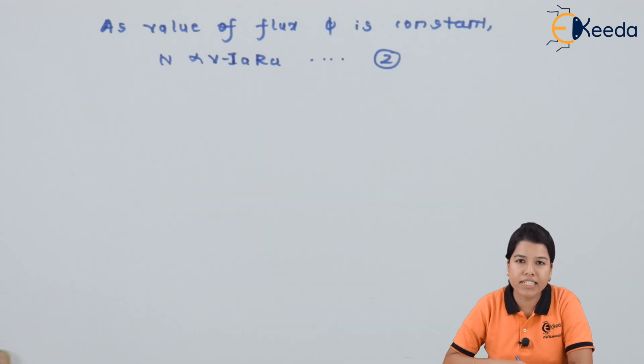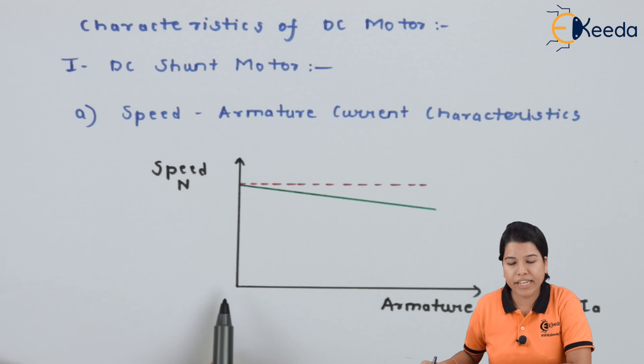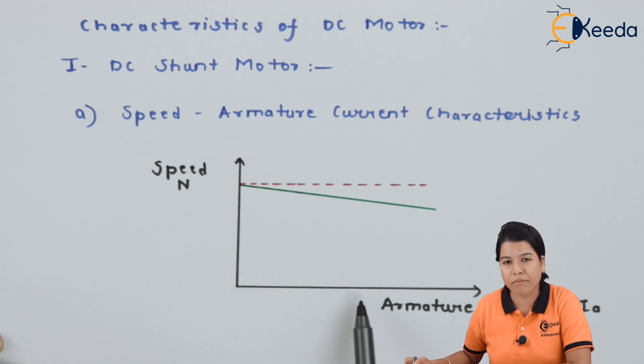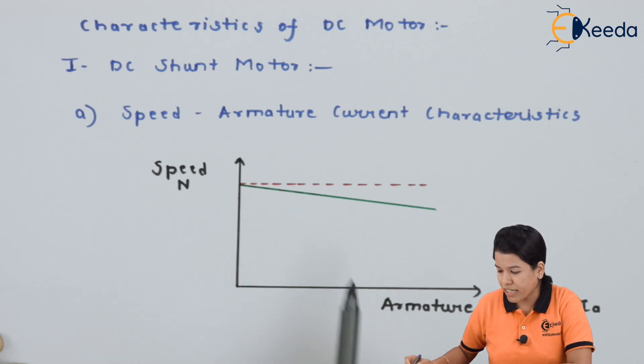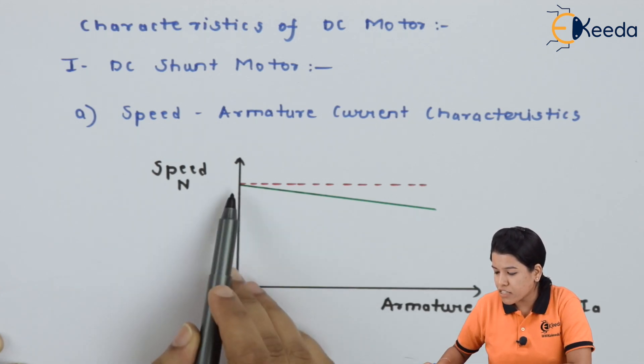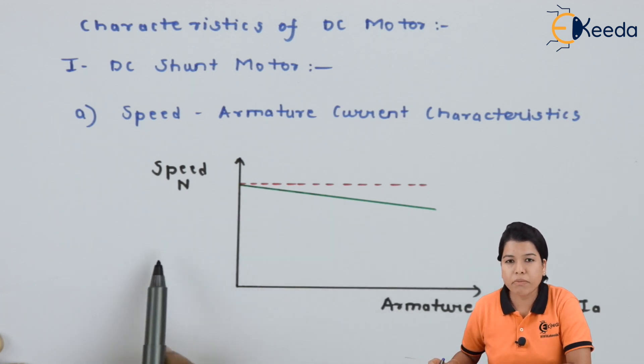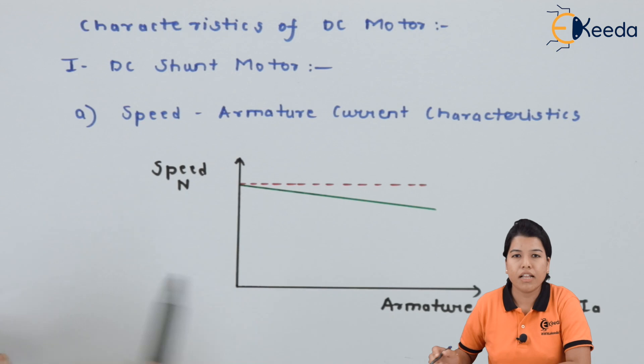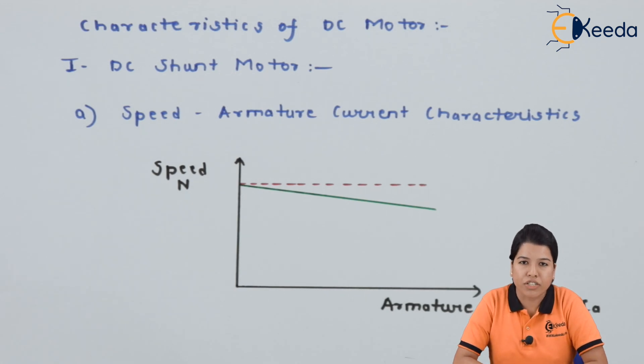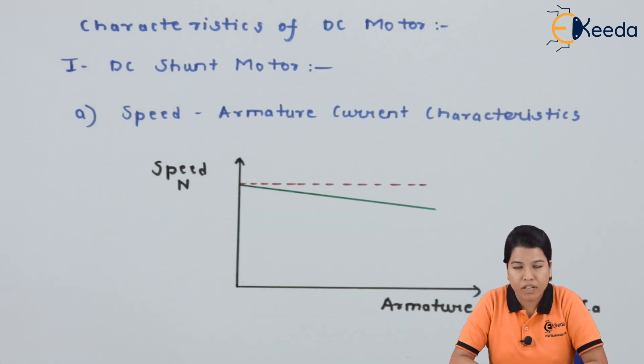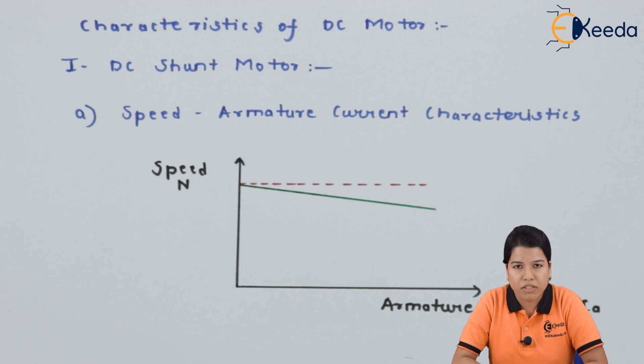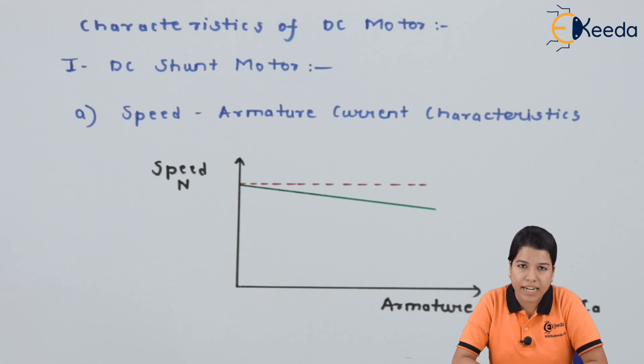Considering this, the characteristic can be drawn as shown. We can see the characteristic of speed versus armature current for DC shunt motor — as the armature current increases, the speed decreases. However, at no-load condition, the term Ia·Ra is very negligible, so the point subtracted from V is also negligible. As V is constant, the speed also remains almost constant. Hence, we can say that the DC shunt motor has almost constant speed.